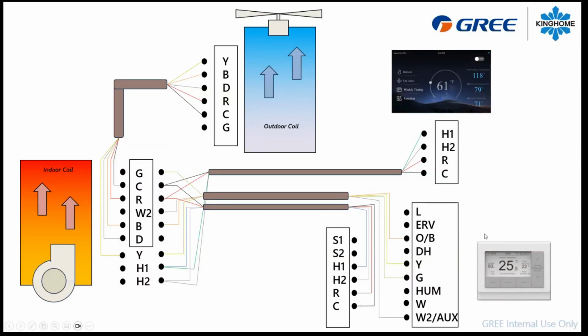From the primary thermostat, while using your KingHome thermostat, I suggest using 2 different wires, one with 4 wires to do your H1, H2, R, and C connection on one side, and you can have another wire driving the reversing valve, the compressor call, the fan call, and W2 aux for your duct heater. And if you have optional stuff like a humidifier, you can have an extra wire on HUM, for example, that is driving inside the air handler. So you can do all your connections here in the electrical box inside the air handler.